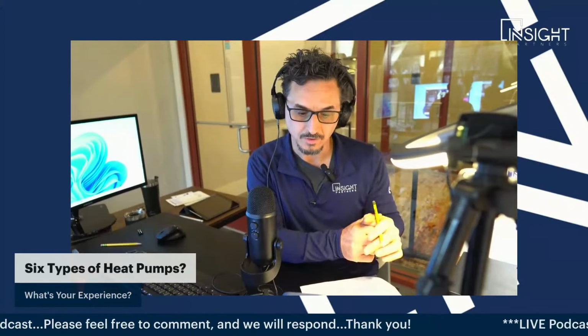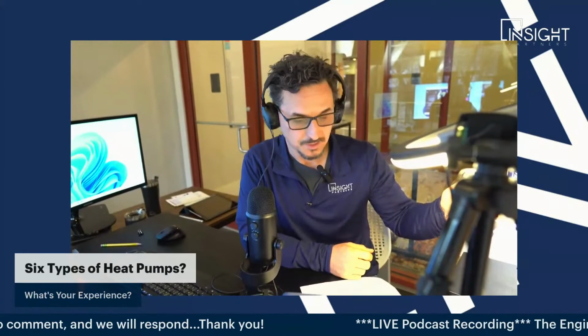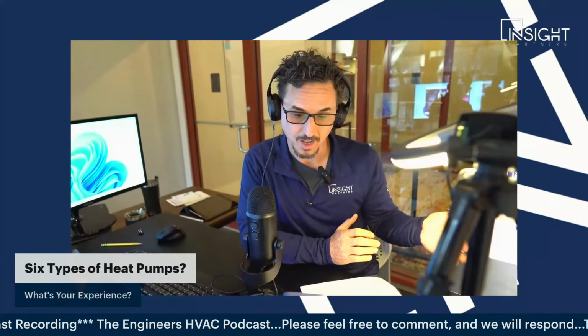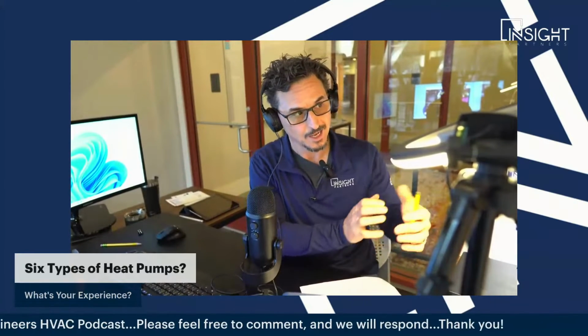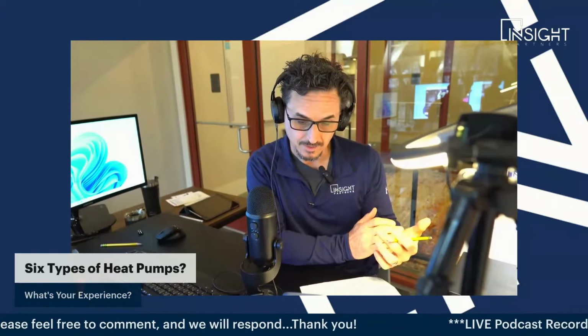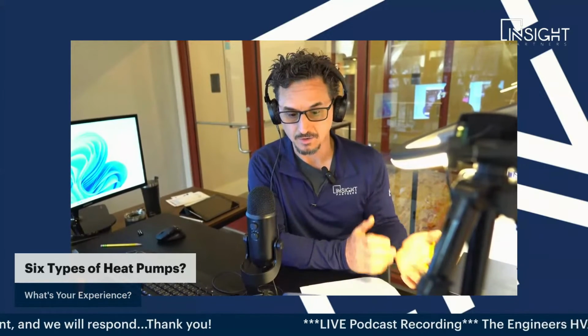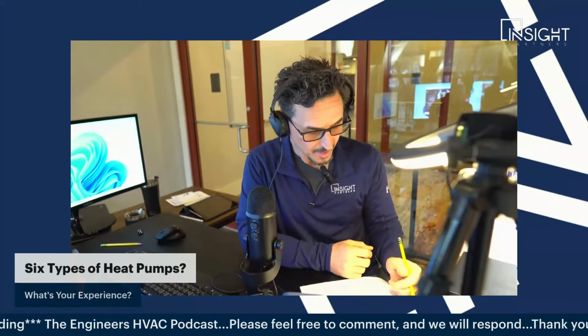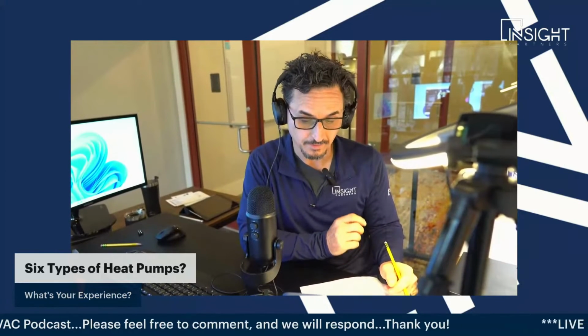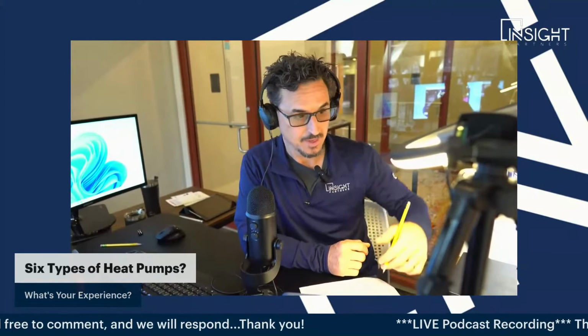Heat pump water heaters are built to extract the BTUs from the ambient air and put that into the water. These are very common in residential applications and becoming more common in commercial applications. A heat pump water heater looks to me like an air-cooled chiller—if you've seen an air-cooled chiller, it's got a big condenser coil, big condenser fans, and a chiller barrel at the bottom. Heat pump water heaters look very similar to that. They could be either outdoors or indoors.